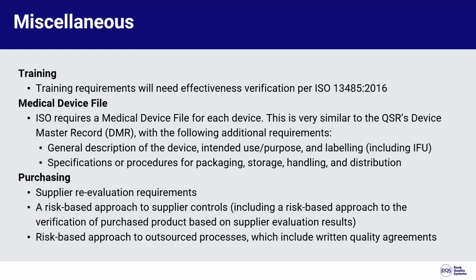Then purchasing has a couple of significant changes, including supplier reevaluation requirements. Currently under the QSR, you are required to evaluate your suppliers, but there's no strict framework for the reevaluation of these suppliers. That changes under the ISO 13485 and QMSR updates. You're also required to take a risk-based approach to supplier controls, including that risk-based approach also applying to the verification of purchased product based on supplier evaluation results.